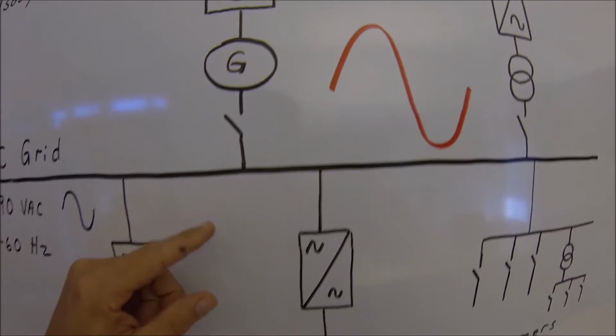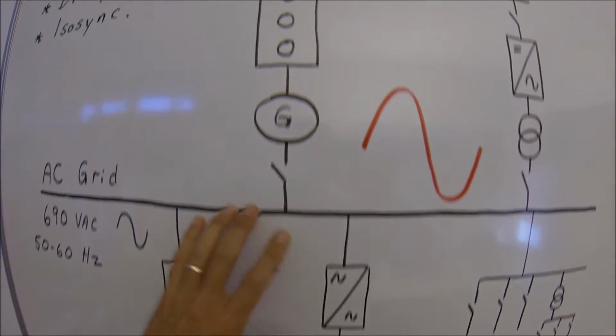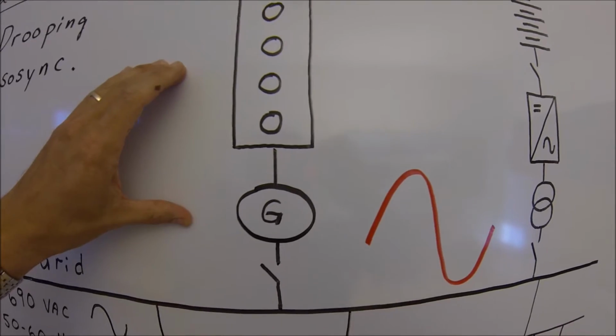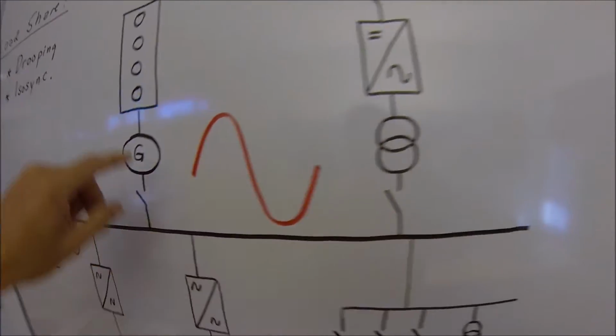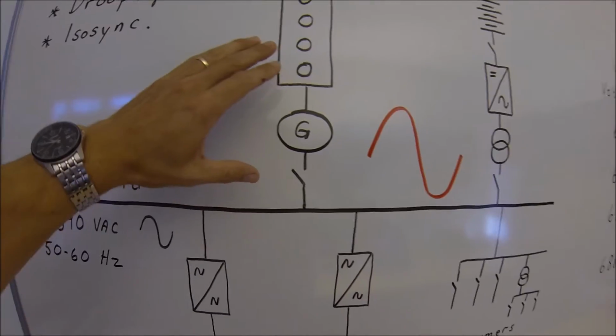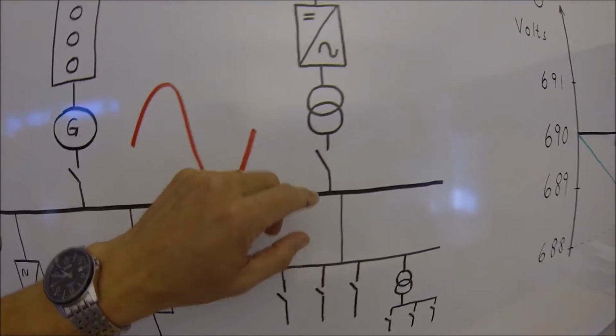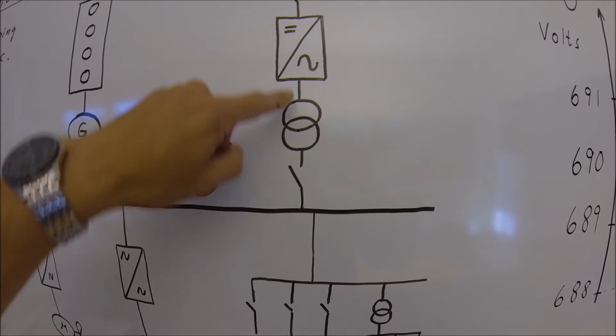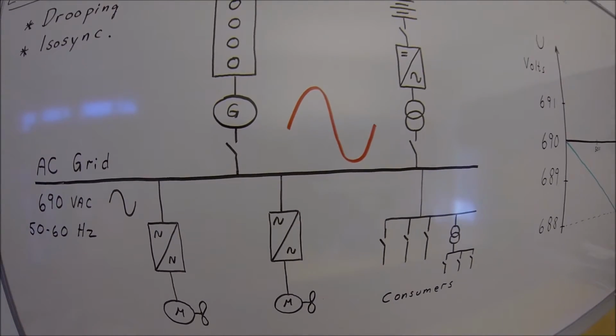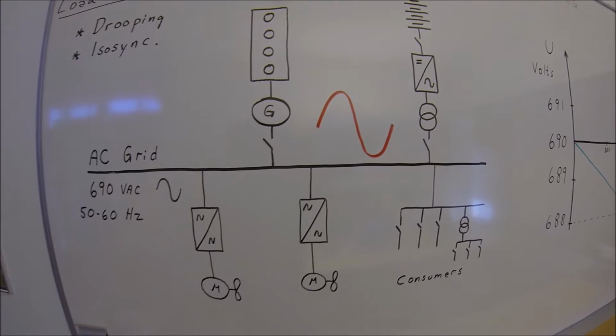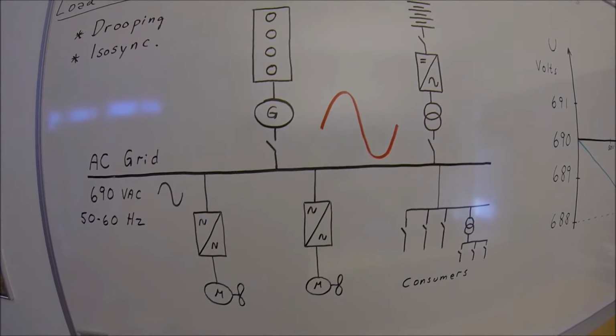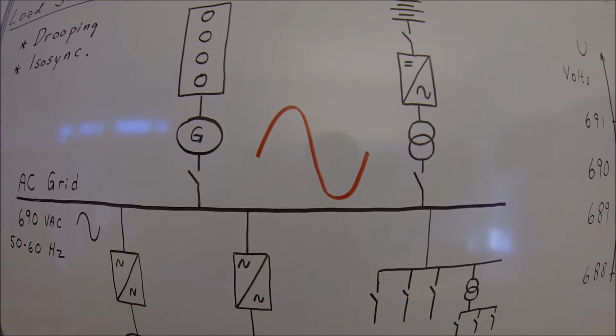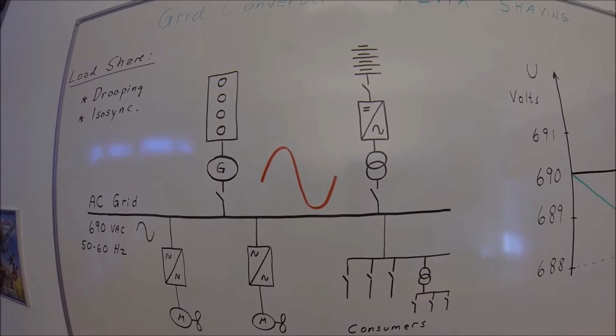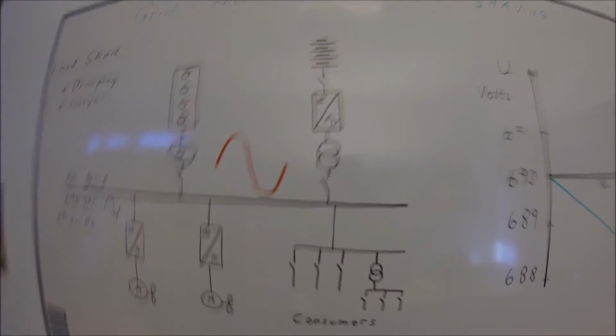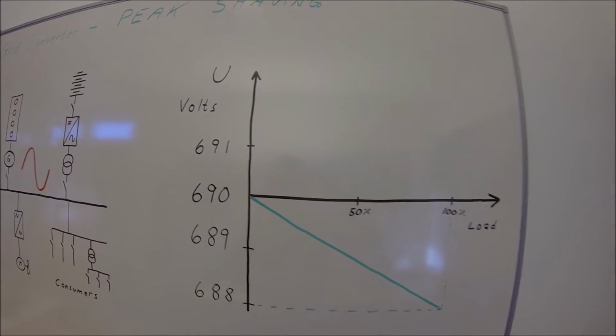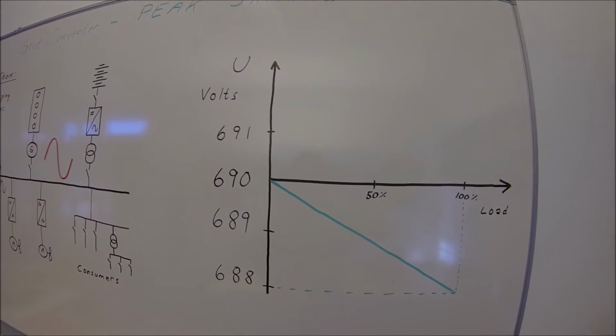When there is a voltage difference between the grid and this energy producer, the diesel generator and the energy storage, there will be a reactive current flowing from the generator and also from the energy storage. This reactive current needs to be controlled in some kind of way. And we use a drooping function also for the voltage. This drooping function for the voltage is very similar to the frequency drooping.